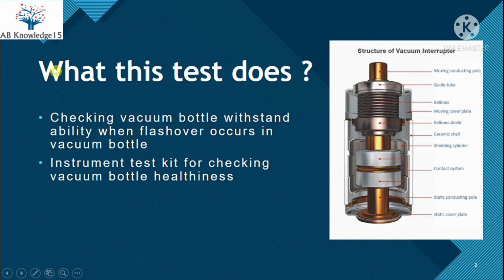First of all, we will discuss what this test does. In this picture I have shown an inside view of a VCB bottle. This one is the moving pole of the breaker and this one is the static pole of the breaker. So this test checks the withstand ability of this vacuum bottle when flashover occurs in it.